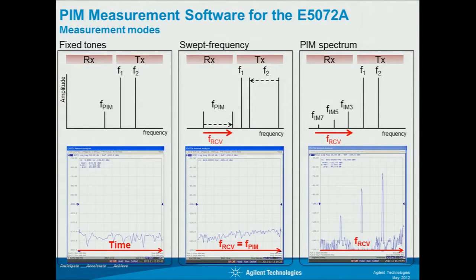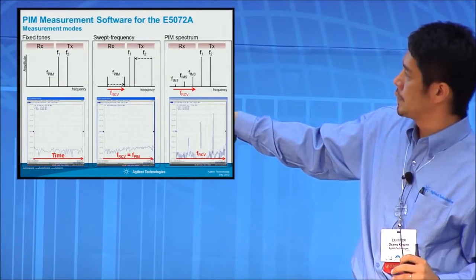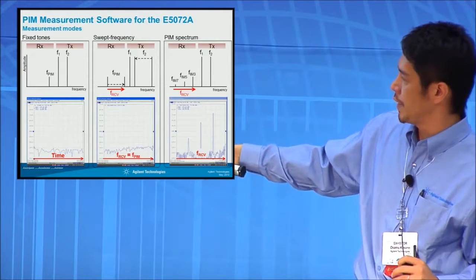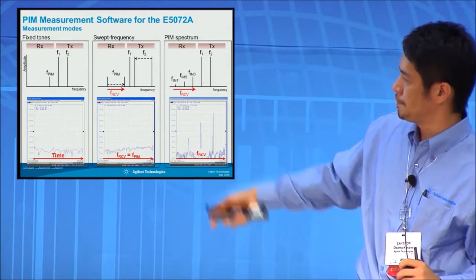The third mode is PIM spectrum. If you put two fixed frequencies and sweep the receiver, you can measure like a spectrum analyzer.